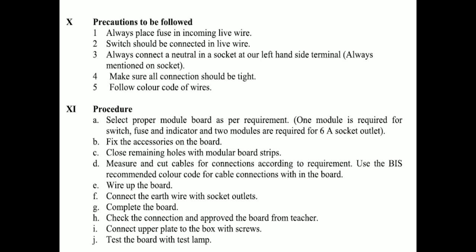Precautions to be followed while performing. We have to follow the precautions which are mentioned here. Always place the fuse in the incoming live wire. Switchboard switches should be connected in the live wire only. Always connect the neutral in the socket at our left hand side. We have to always connect the neutral at the left hand side of the 3-pin socket, and on the right hand side we have to connect the phase wire.